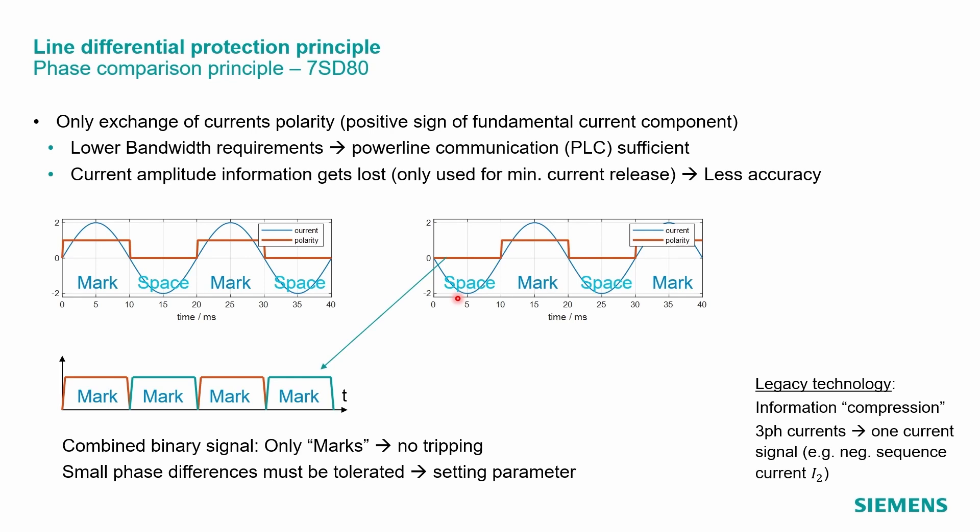The local binary sequence of marks and spaces is combined with the received binary information, as shown here. The combined binary signal only contains marks for the external fault. And this does not lead to a trip condition. Small gaps due to phase errors must be tolerated and stabilized by some settings.